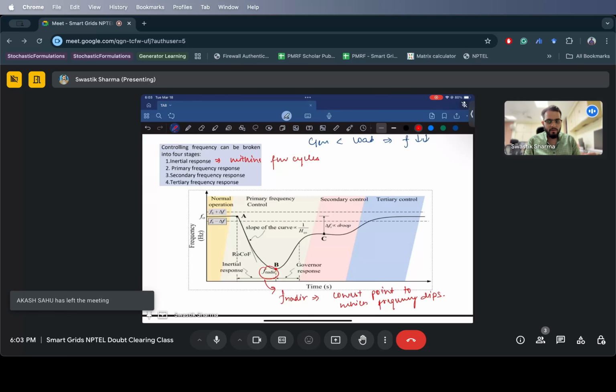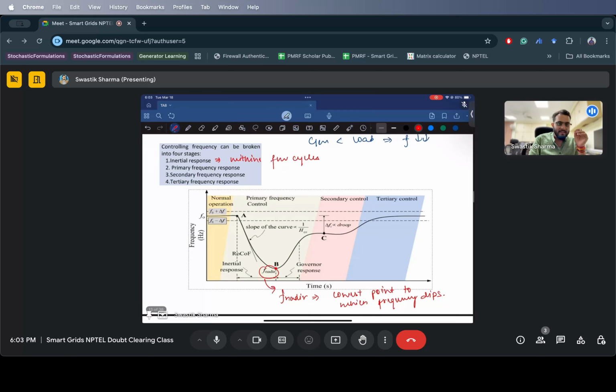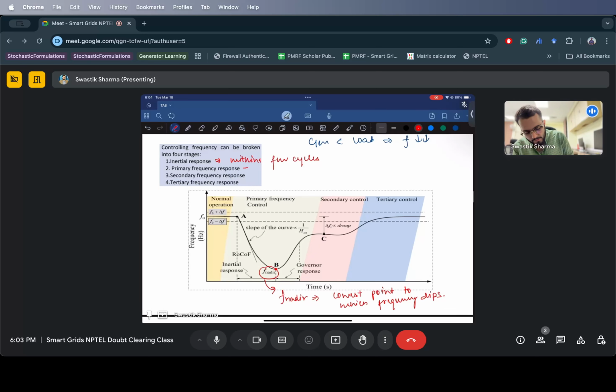Right now, it has arrested the frequency nadir. It has arrested the ROCOF from deteriorating further. Now, it is not sufficient. The inertial response in itself is not sufficient to arrest this dip. What it now does is it moves on to the primary frequency control. So the next response that comes is primary frequency control.